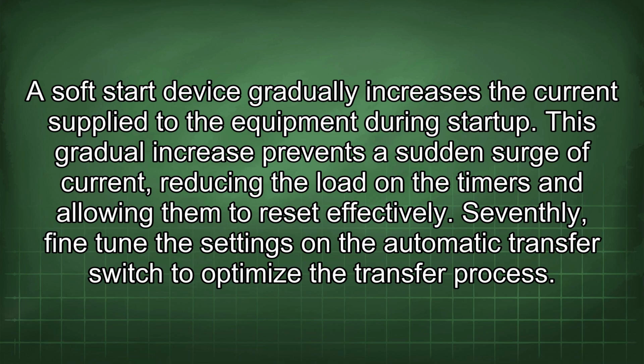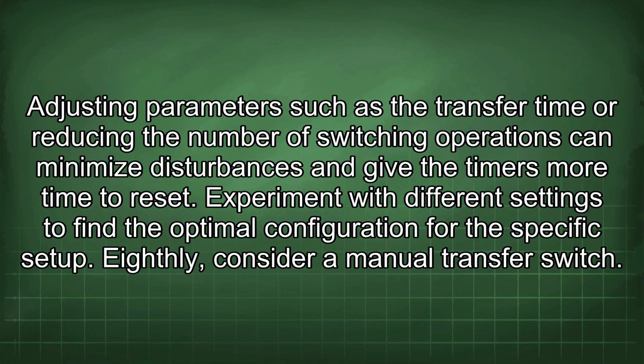This gradual increase prevents a sudden surge of current, reducing the load on the timers and allowing them to reset effectively. Seventhly, fine-tune the settings on the automatic transfer switch to optimize the transfer process. Adjusting parameters such as the transfer time or reducing the number of switching operations can minimize disturbances and give the timers more time to reset. Experiment with different settings to find the optimal configuration for the specific setup.